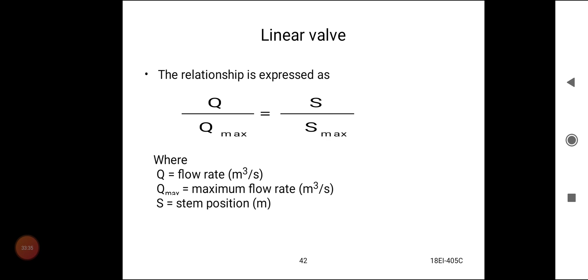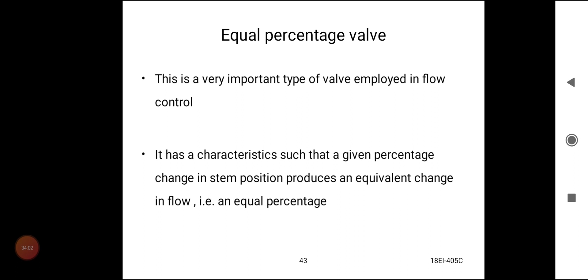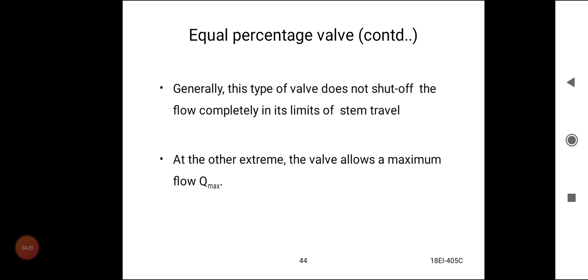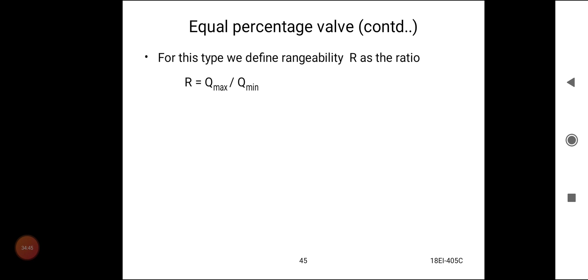Equal percentage valve. This is a very important type of valve employed in flow control. It has characteristics such that a given percentage change in the stem position produces an equivalent change in flow, that is, an equal percentage. Generally, this type of valve does not shut off the flow completely at its limit of the stem's travel. At the other extreme, the valve allows maximum flow Q maximum. For this type, we define rangeability R as the ratio between Q max and Q minimum.